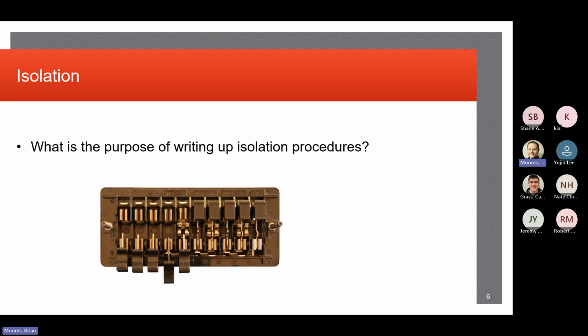So these test switches offer isolation points for inputs and outputs to protective relays, right? So it gives you a point of disconnection or isolation, whether it could be an input or for a logic input, it could be an output that does a tripping function. It could be voltages and currents, right? Because the relays need voltages and currents in order to make decisions, right? That's what they're looking at. The relays are really looking at voltages and currents and the relationship between them to make decisions, right? That's ultimately what the relays are for. And depending on the application, they look at a series of whatever impedance or overcurrent or voltage or whatever. It depends on the relay. We talked about distance relays last time. So what this allows us to do is isolate the relay, but we can also use this as a test block.